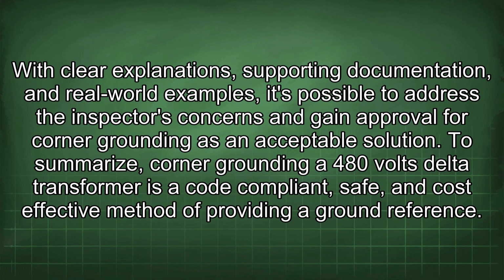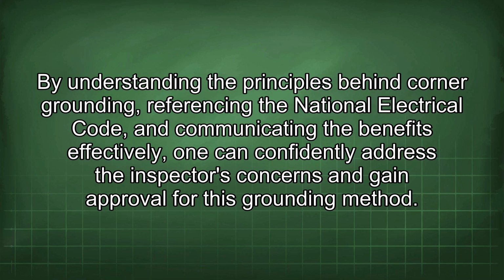To summarize, corner grounding of a 480-volt delta transformer is a code-compliant, safe, and cost-effective method of providing a ground reference. By understanding the principles behind corner grounding, referencing the National Electrical Code, and communicating the benefits effectively, one can confidently address the inspector's concerns and gain approval for this grounding method.